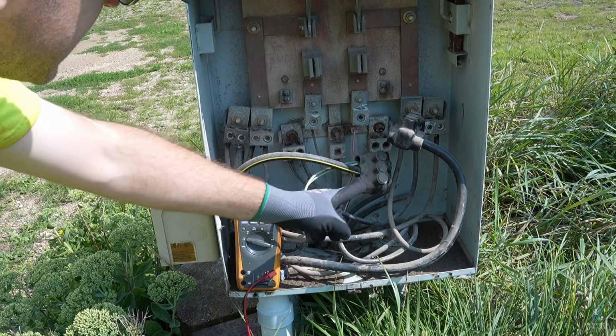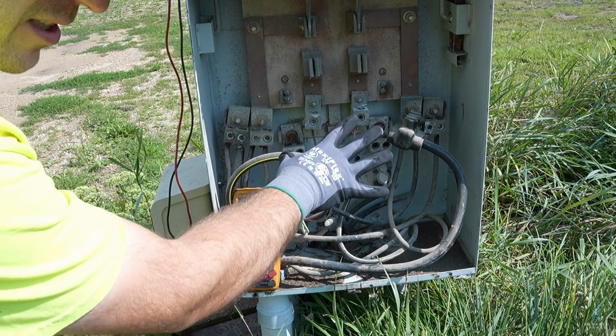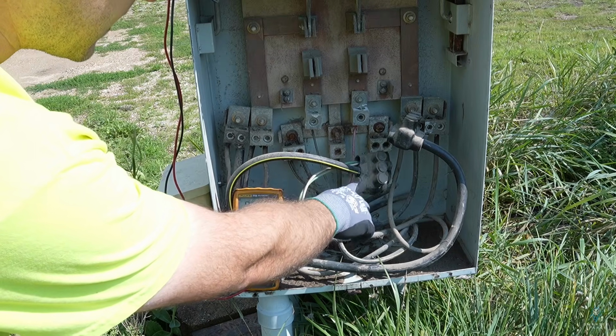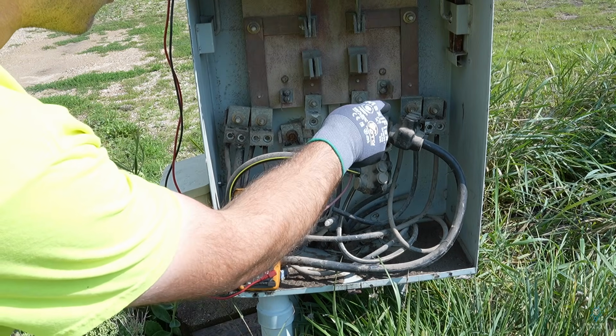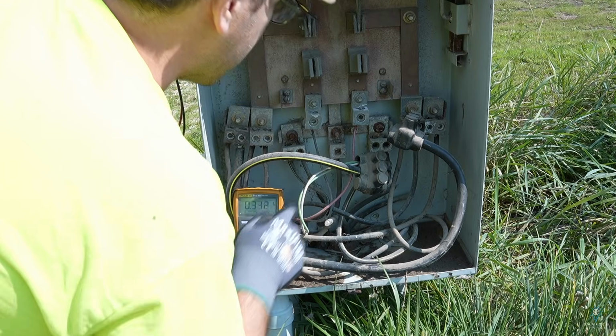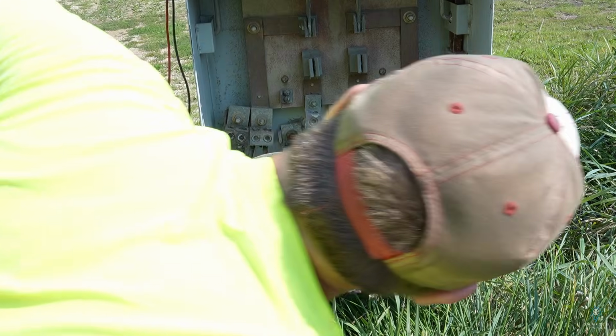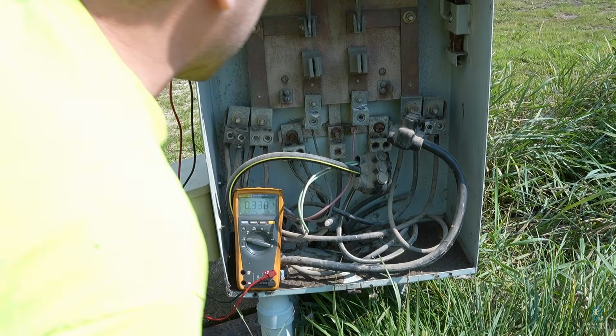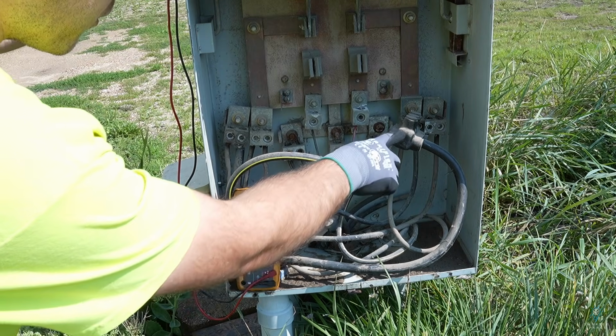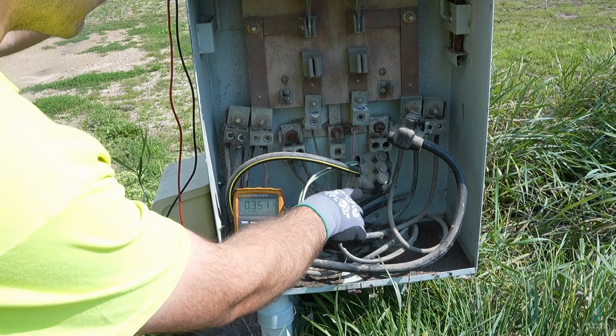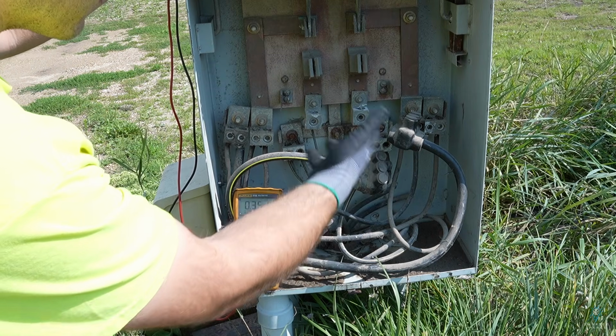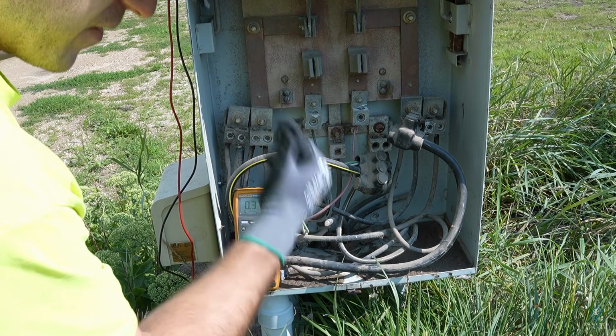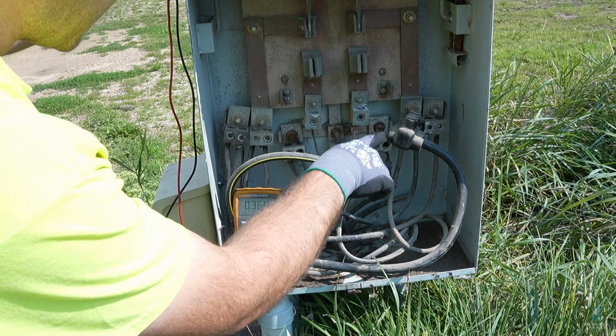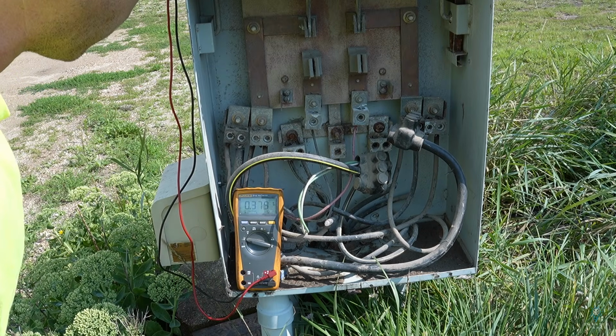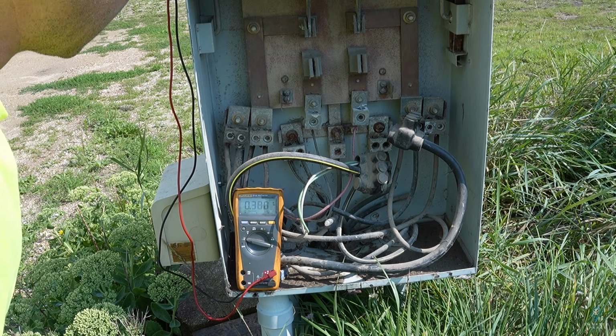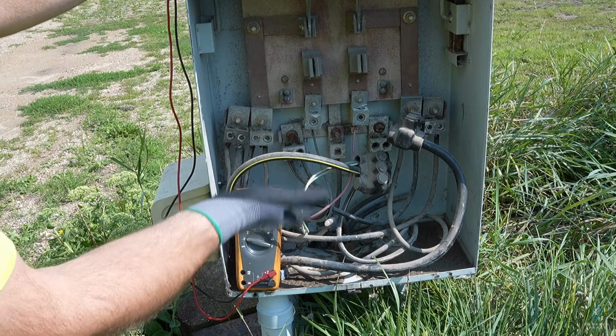So what they did is they spliced on, I don't want to be messing with stuff while this is energized, but they spliced these Polaris connectors on because they couldn't get the lugs off. It does look like the heads have been stripped out slightly, like somebody tried to replace them but couldn't. So I'm pretty sure the reason these 2 Polaris connectors are here is because when they originally did this service change 15, 20 years ago in the house, when they spliced on here, they didn't even want to mess with the old corroded lugs in this disconnect here, this transfer switch. This is actually a transfer switch.